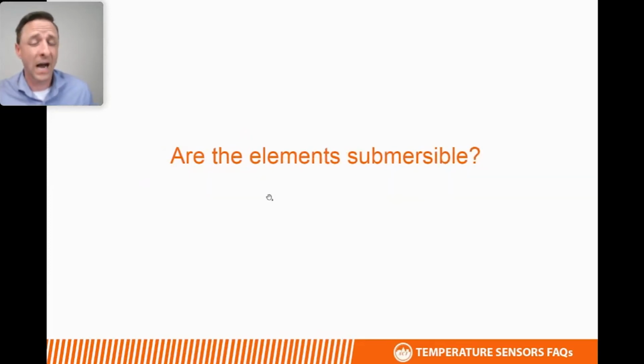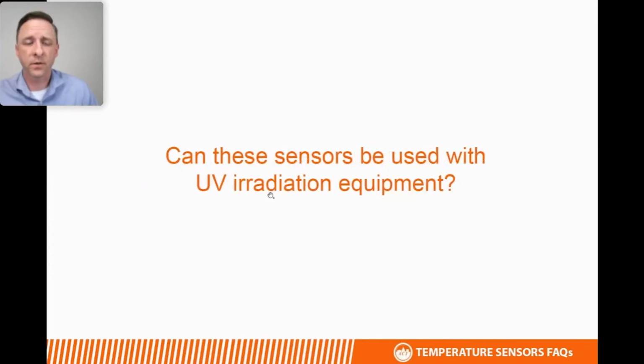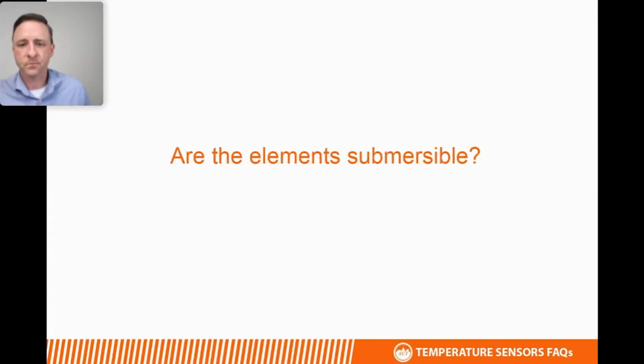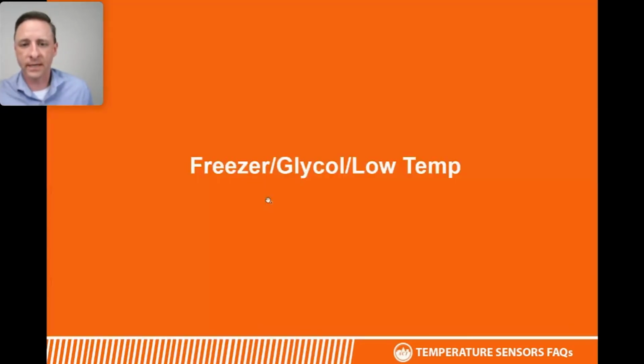Can averaging sensors be used with UV irradiation equipment? Yes and no. The copper averaging can, but the flexible averaging should not be used with UV equipment. Are these elements submersible? So we've had that question. People want to drop the averaging sensor into a tank and get an average of the water temperature in a large tank. And nope, do not do that. These elements are not watertight and should not be submersed in any kind of tank.